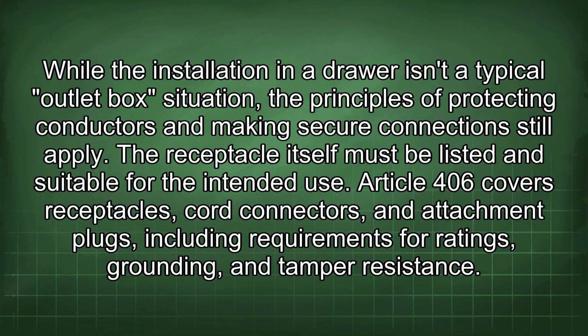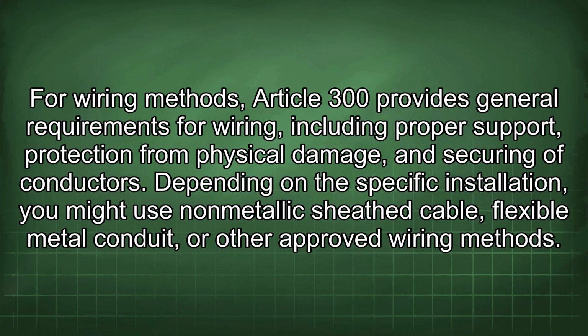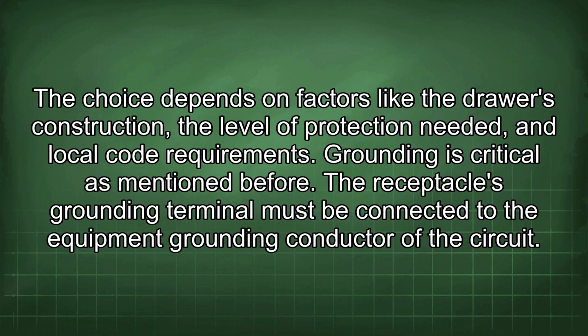Article 406 covers receptacles, cord connectors, and attachment plugs, including requirements for ratings, grounding, and tamper resistance. For wiring methods, Article 300 provides general requirements for wiring, including proper support, protection from physical damage, and securing of conductors. Depending on the specific installation, you might use non-metallic sheath cable, flexible metal conduit, or other approved wiring methods. The choice depends on factors like the drawer's construction, the level of protection needed, and local code requirements.